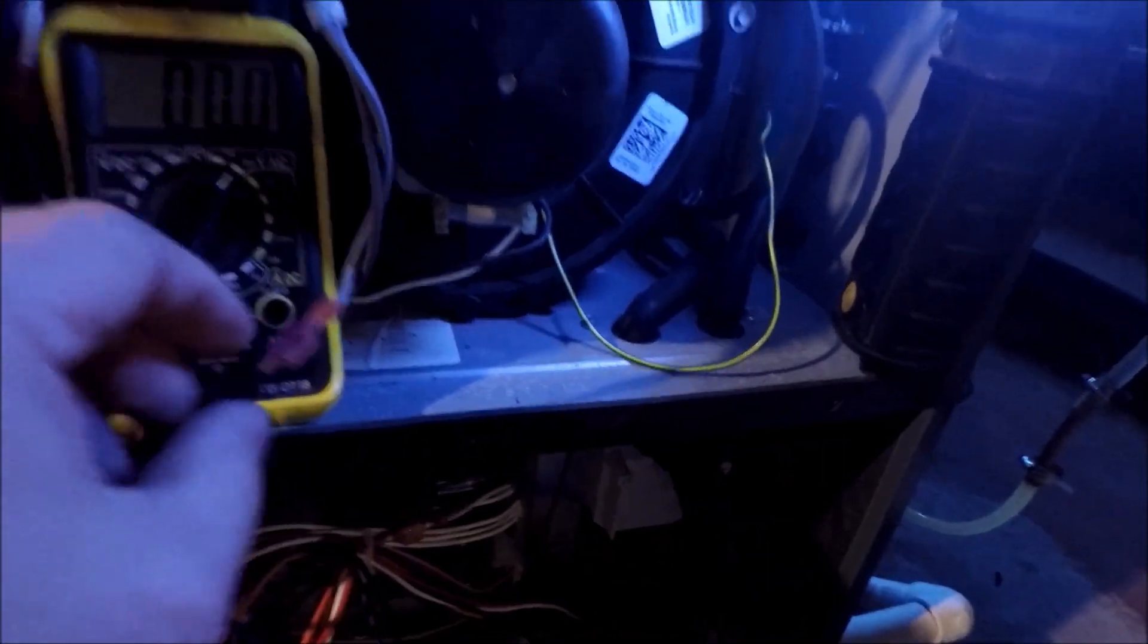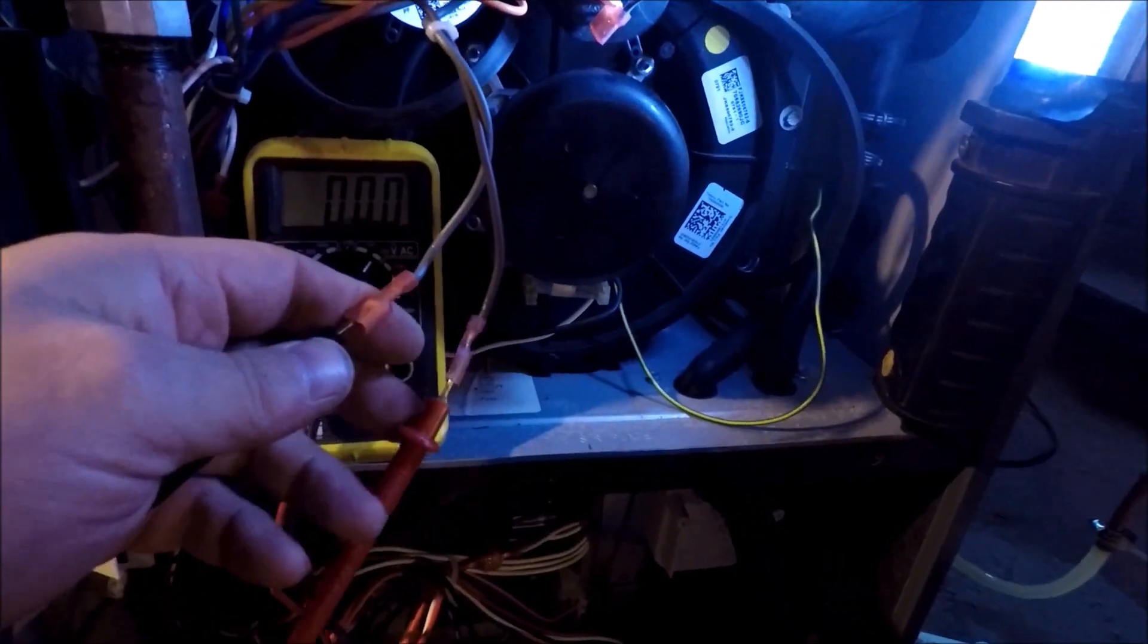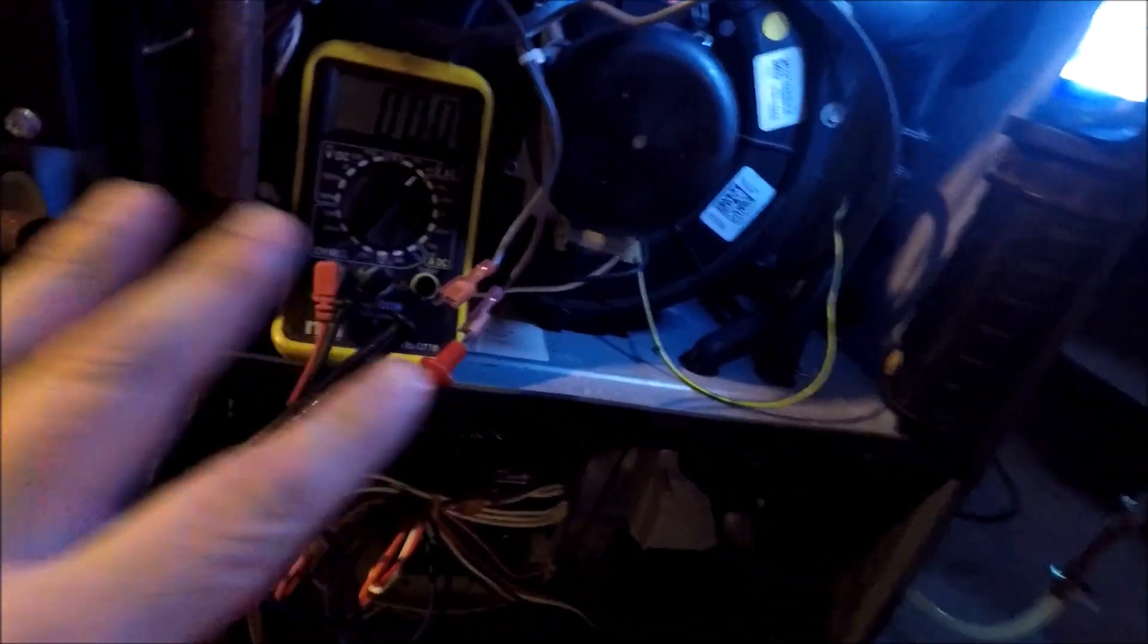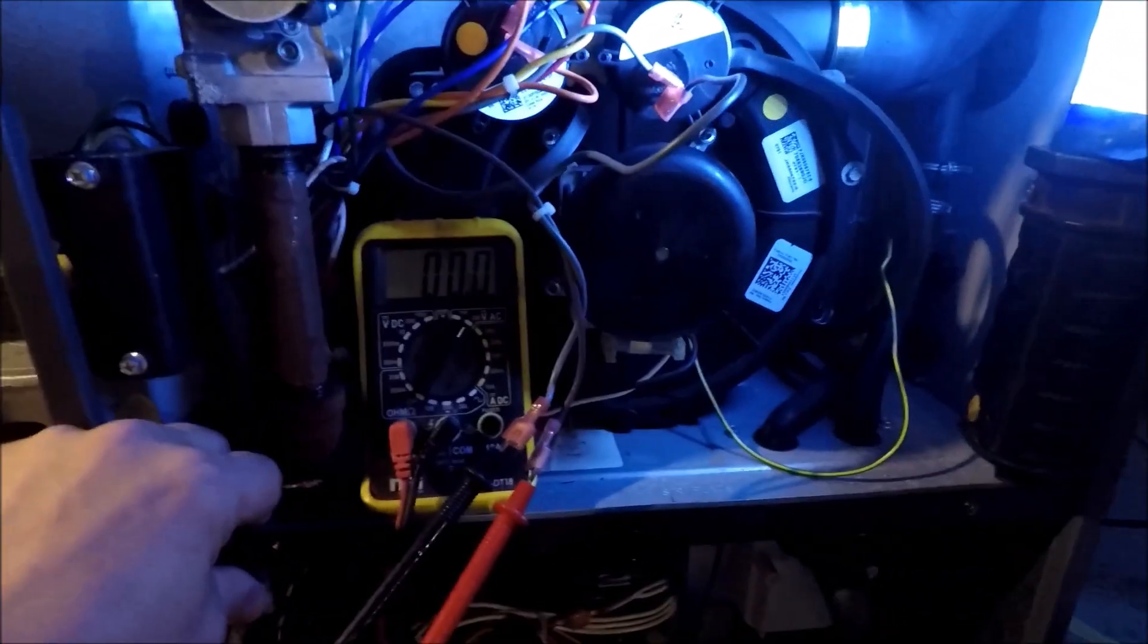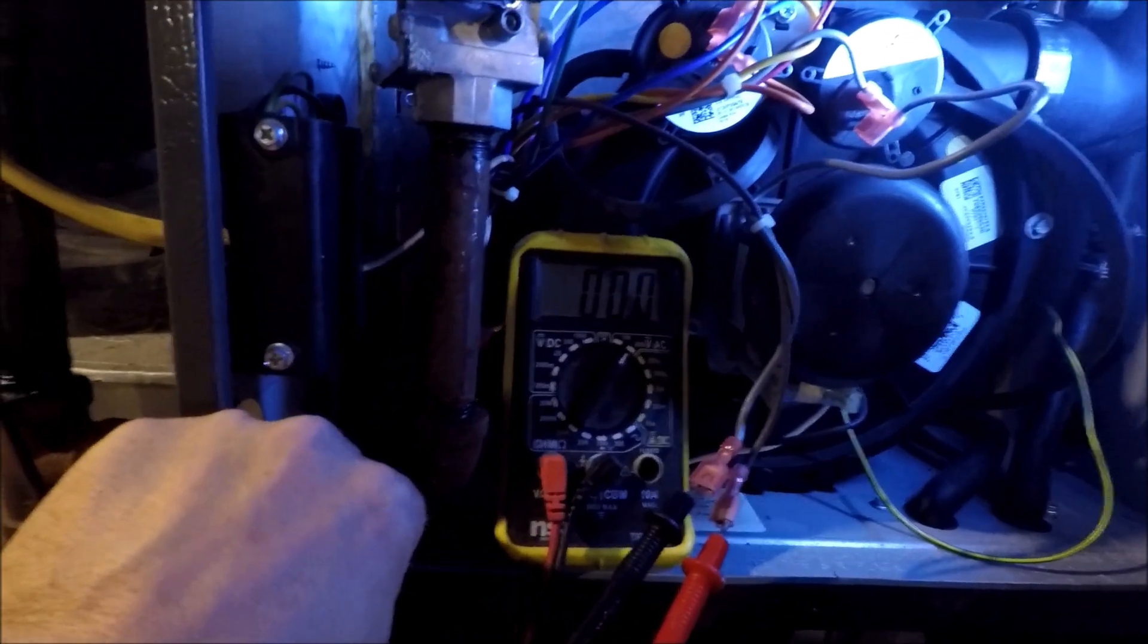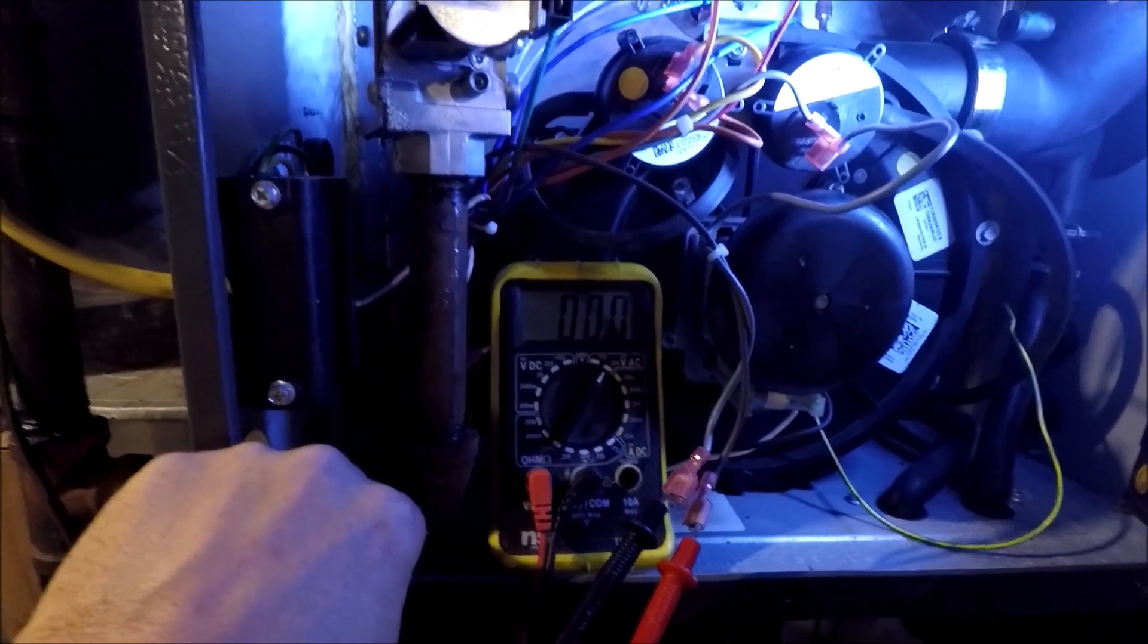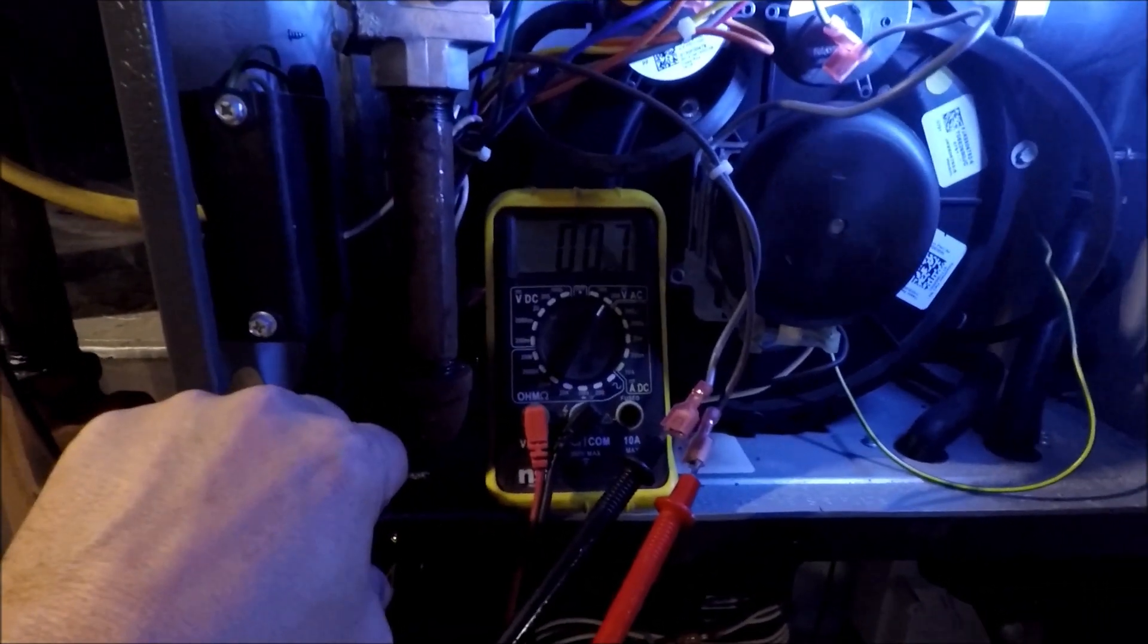And we have our probes hooked up to our gas valve connections. We're looking for 24 volts. Right now there's no voltage there. So if we get a change in voltage, we know we're getting 24 volts to the gas valve and it should come on.